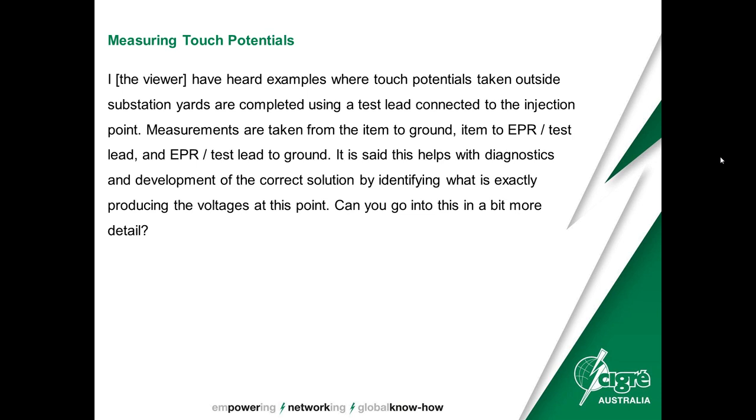I can. Do we know who asked the question? That was me. Yeah. I remember doing it when I was down there doing Safe Earth training. Okay. My question was going to be, where did you see that? Because it's a good technique, but to my knowledge, others aren't doing it. So yeah, I tried to tell the boss about it, and they're like, oh, yeah, maybe not. The risk of running the EPR lead out, I don't know about that, so it hasn't been done. Okay, well, that's a fair consideration. There are certainly places where we would decide that you don't want to run the EPR lead to a certain location, and we'll settle for just doing other measurements at that location.